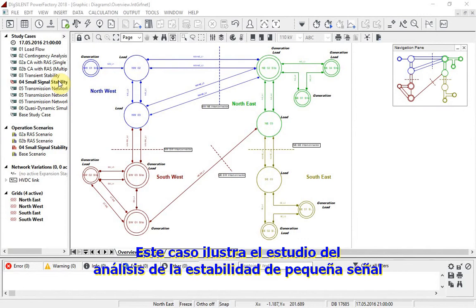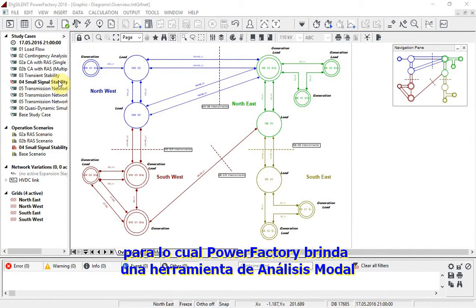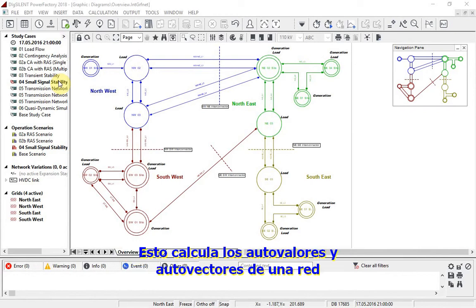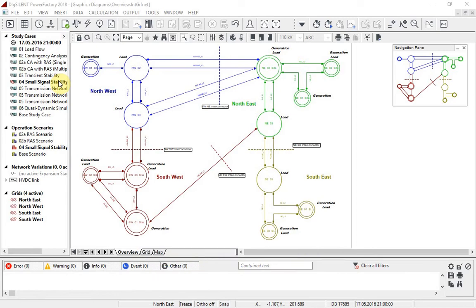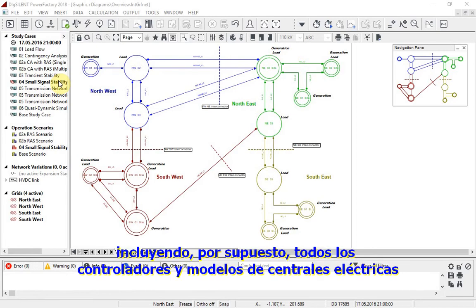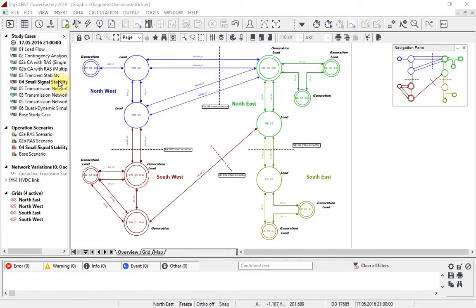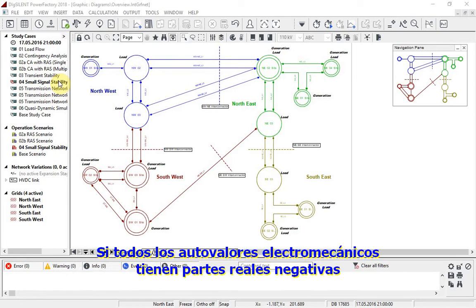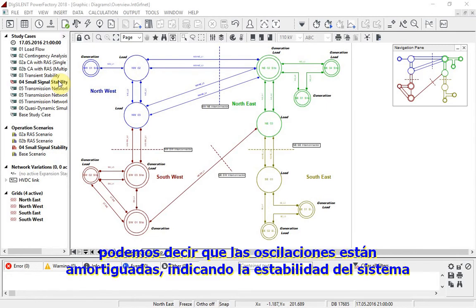This case illustrates the study of small signal stability analysis, for which Power Factory provides a modal analysis tool. This calculates the eigenvalues and eigenvectors of a network, including all controllers and power plant models. If all the electromechanical eigenvalues have negative real parts, we can say that the oscillations are damped, indicating system stability.